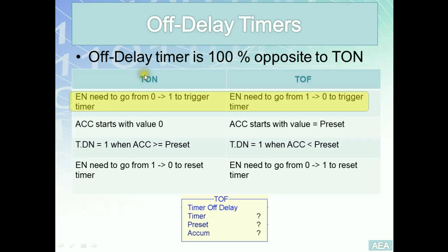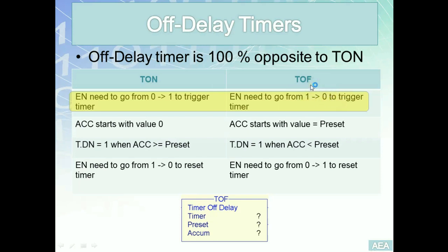On the other side for the TOF it's 100% opposite. It means we need to have logic discontinuity across the rung. This will disable the enable bit and once the enable bit goes from one to zero, this actually will trigger the TOF and it will start timing at that point.